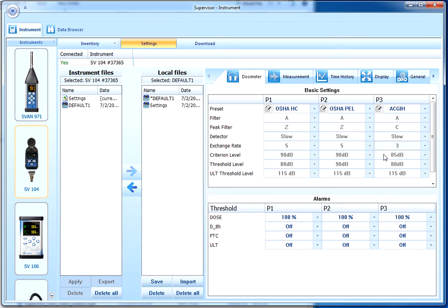each of the profiles. This means, for example, for somebody working in a noise level of 90 dB, it would take 8 hours for them to be exposed to the noise before the 100% level was reached. That's basically the end of their shift. So you wouldn't know that an alarm condition had existed until the very end of the shift, right at the end of the 8 hours.